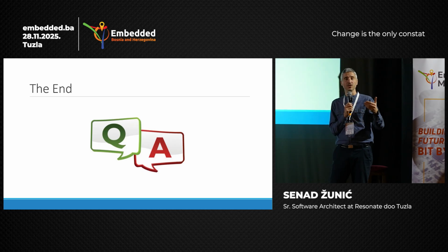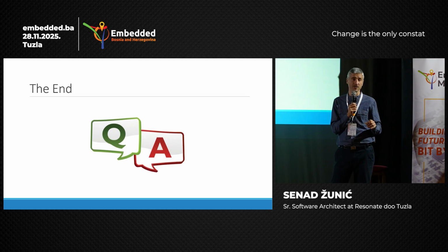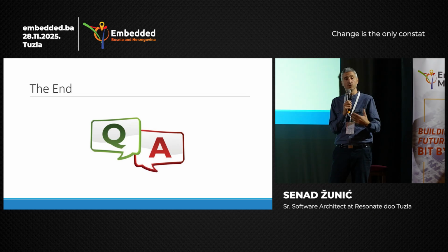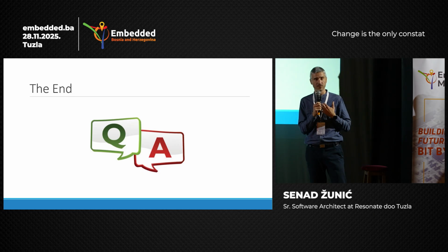If it does, in your own verification of the software, you need to include testing of that specific service. So you can, in your own tests, write tests for that SOUP. So you take responsibility for testing.